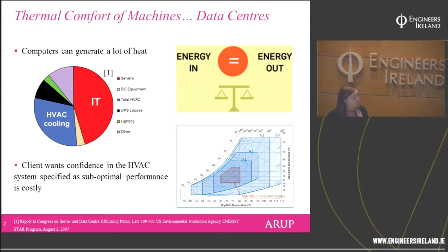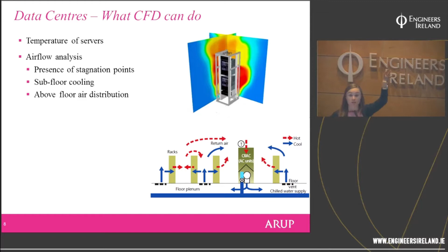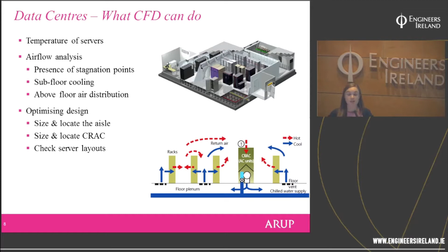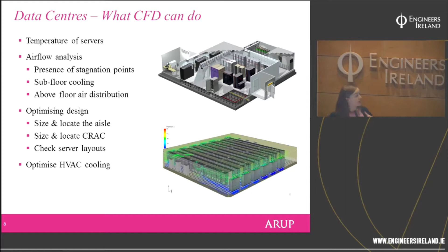With CFD, computational fluid dynamics, we can look very specifically at the temperatures of the servers, how they heat up and cool down. We can assess the risk of stagnation points, where there might be very hot zones and very cold zones without enough mixing. We can examine where the cooling units and floor grills are placed, and ultimately optimize the cooling system for a particular data center design.